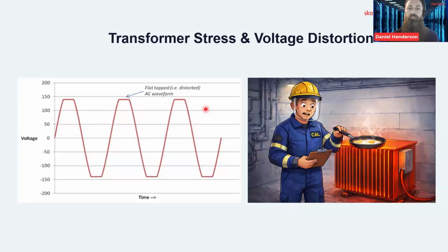And it's good to see this actually, it's not good to see when you're responsible for the network. But I've had quite a few issues of this, especially in facilities that have developed over time. So I've had one where I had two transformers sat next to each other, sister transformers feeding one common LV switchboard. Previously, they had a lot more linear load on each side, one or two production lines on each side of the board with the bus coupler open. And again, the load difference, one had a higher FHL than the other, and the difference to physically see that was around 25 degrees C in oil temperature between the two, even though the load was theoretically the same. And so it was really good to see that.